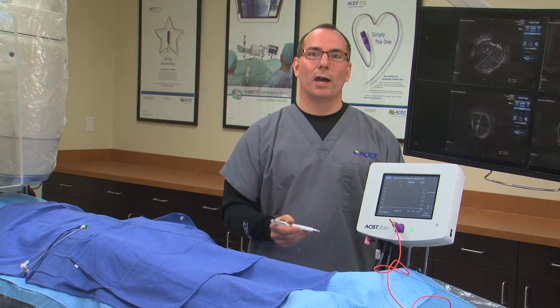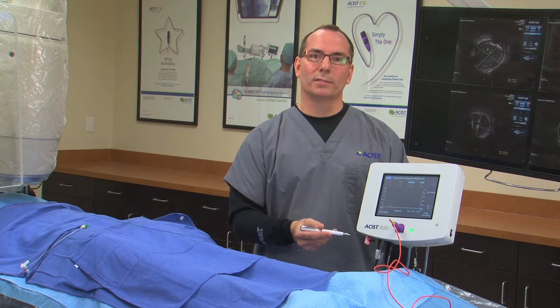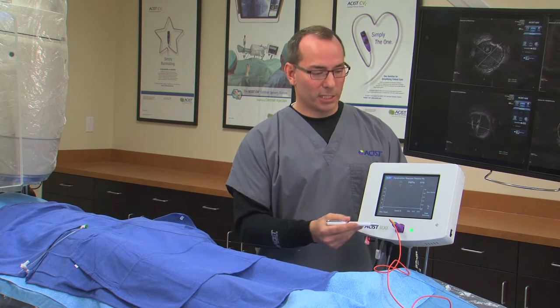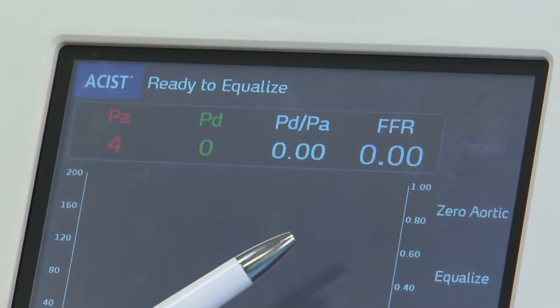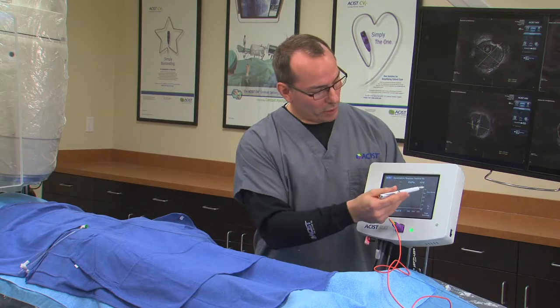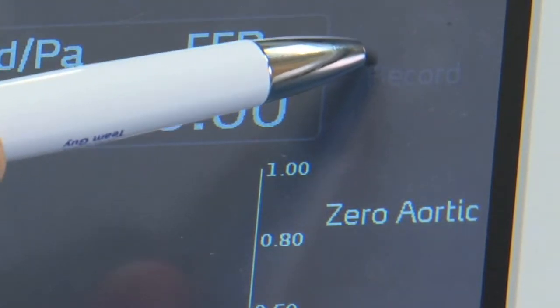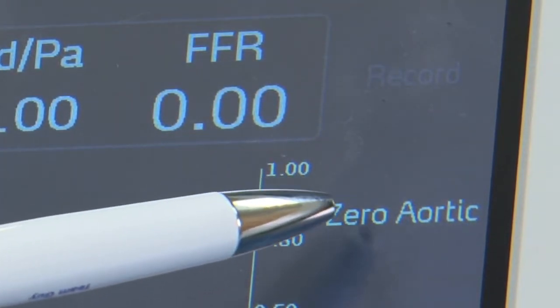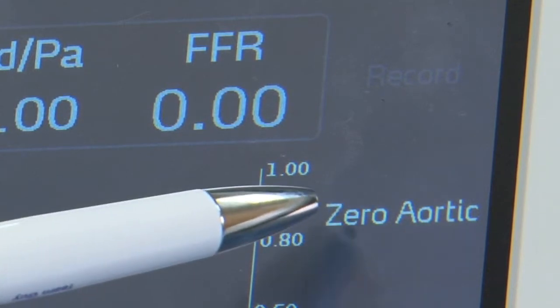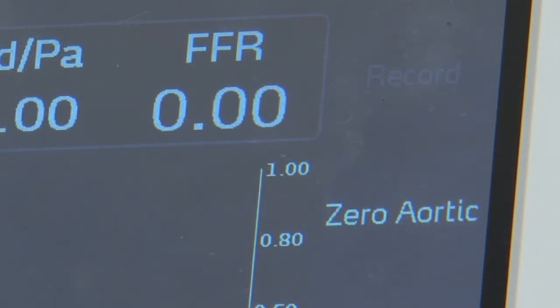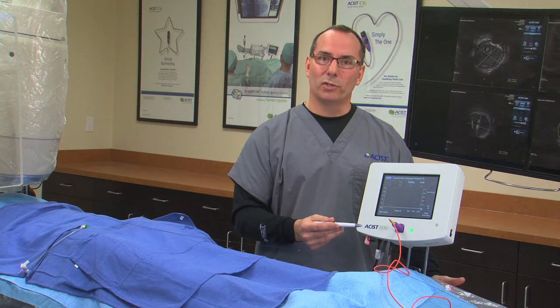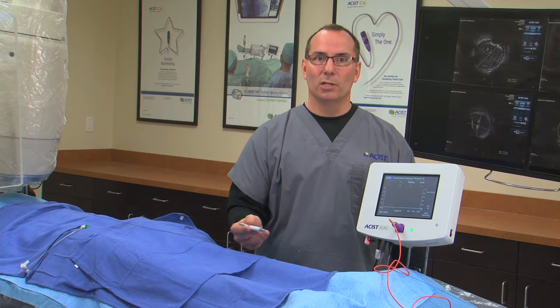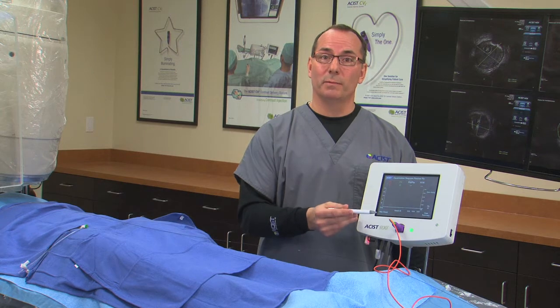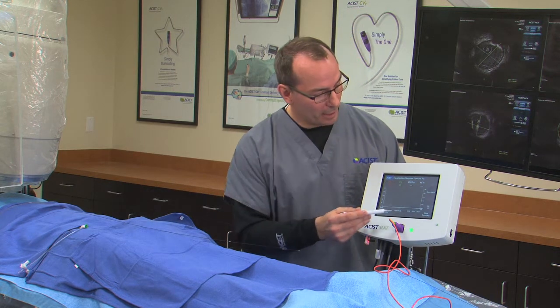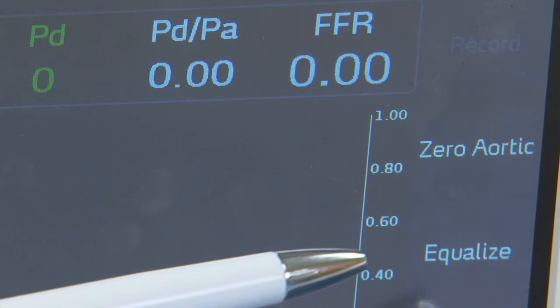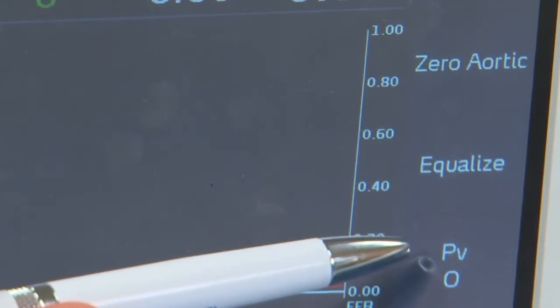When recording, the Rxi Console will track the pressure gradients, calculate the FFR, and display the value here under FFR. Working around the screen, the record key, or the record button, records the hyperemic response, then is the zero aortic button. Now the zero aortic button is only used at the time of install. Then we pair or match this system with the hemodynamic system, so you no longer have to zero the system unless you choose to. The next button is the equalize button, followed by the PV button.